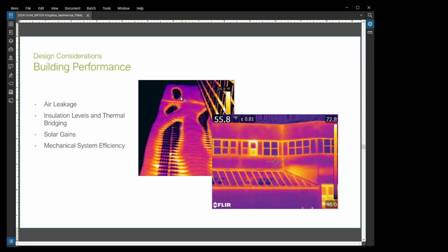Where it's connected in the loop is essentially all the same, because you're doing the same thing, but ultimately the end goal is to raise the ground loop temperature. So if you're injecting it higher up into the loop so it just goes straight into the building, when it runs back down into the ground loop it will have gone up a little bit. Where it goes exactly is up for the designers to figure out as part of the whole sequence of operations. Essentially, because it's all a closed system, the end goal is just to get that ground temperature back up over a period of time, so you don't have to do it anymore.